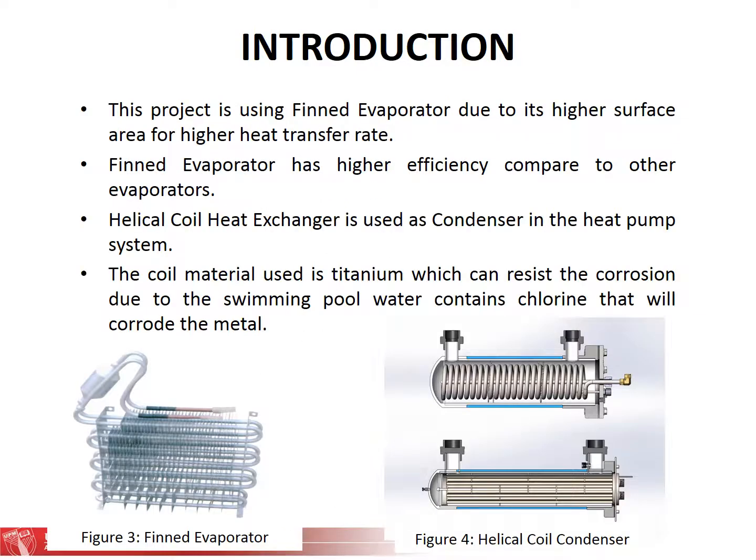This project is using finned evaporator due to its higher surface area for higher heat transfer rate. Therefore, it has higher efficiency compared to other evaporators. Besides, helical coil heat exchanger is used as the condenser in the heat pump system. The coil material used is titanium, which can resist the corrosion due to the swimming pool water contain the chlorine that will corrode the metal.